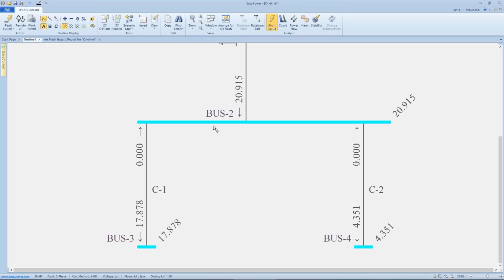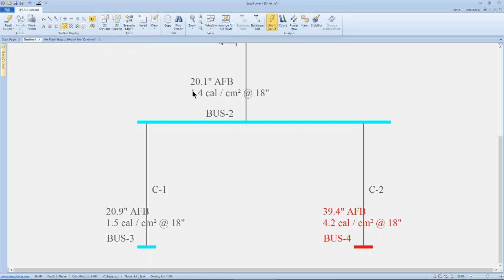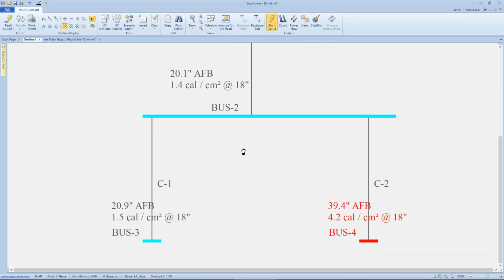Now I'm ready to do incident energy calculations. The arc flash icon is this little burning man symbol on the top row over here. And when we click on that icon, we get new numbers and new colors. And this is where the electrician says, Jim, I think you have a bug in your tools. So, well, what do you mean? He says, well, right here, I see the arc flash boundary on bus 2 is 20 inches. The incident energy is 1.4 calories per square centimeter, so I know what PPE I need to put on to work on this bus hot.